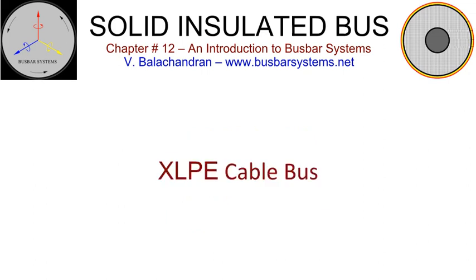XLPE cable bus. Single-core XLPE cables are manufactured for a rating up to 500 kV, and are in operation for the past few decades. While its application is most common for long-distance power transmission for high-voltage and extra-high-voltage systems and various interconnections between equipment, transformers, switchgear and motors, in the medium-voltage system, it can be very effectively used as an alternative to a bus duct under certain ampacity constraints. Not only will such alternatives be more compact and space-saving, but they would also be more economical.